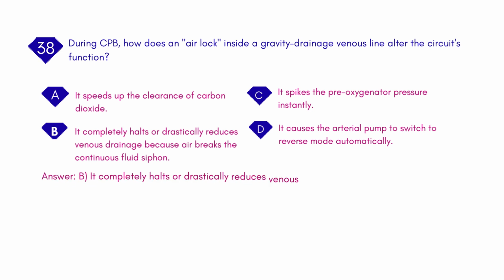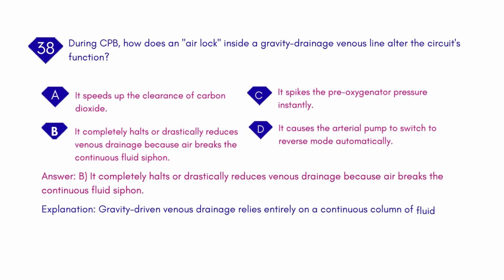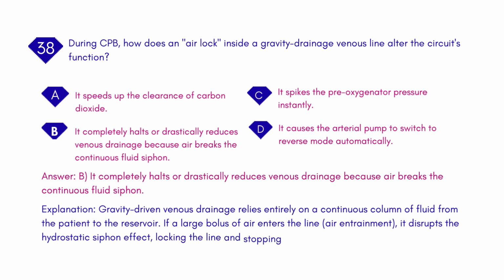Answer: B. It completely halts or drastically reduces venous drainage because air breaks the continuous fluid siphon. Explanation: gravity-driven venous drainage relies entirely on a continuous column of fluid from the patient to the reservoir. If a large bolus of air enters the line, air entrainment, it disrupts the hydrostatic siphon effect, locking the line and stopping all passive drainage into the machine.